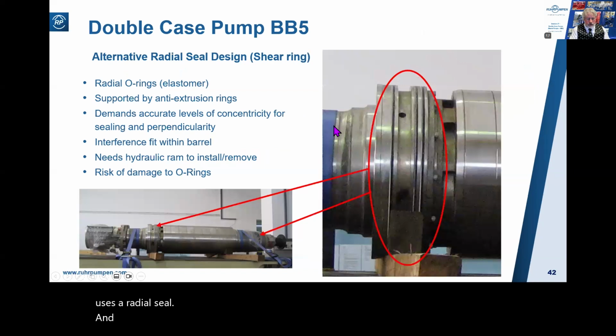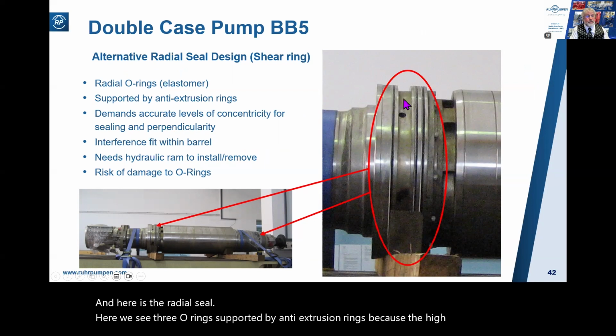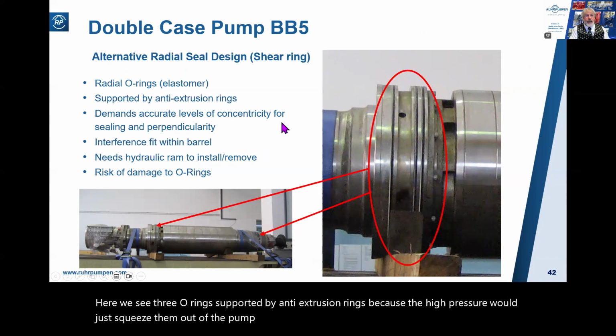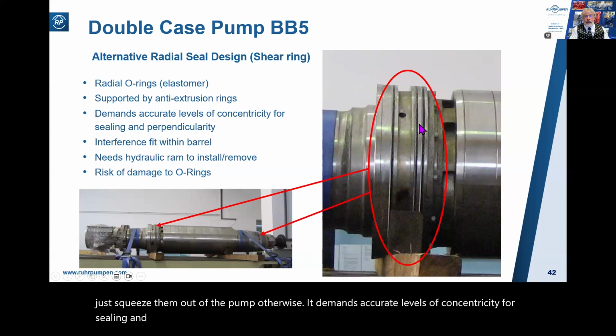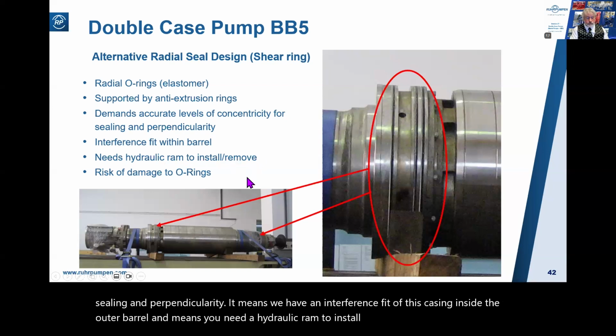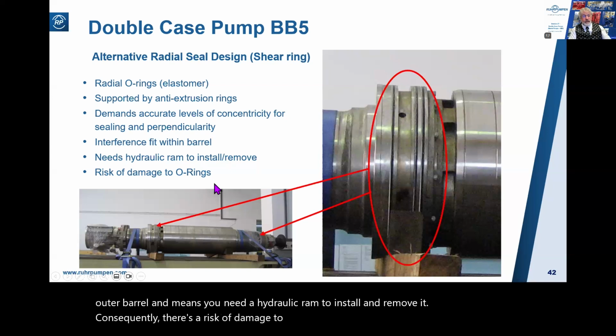And here is the radial seal. Here we see 3 O-rings supported by anti-extrusion rings, because the high pressure would just squeeze them out of the pump otherwise. It demands accurate levels of concentricity for sealing and perpendicularity. It means we have an interference fit of this casing inside the outer barrel, and means you need a hydraulic ram to install and remove it. Consequently, there's a risk of damage to the O-rings there.